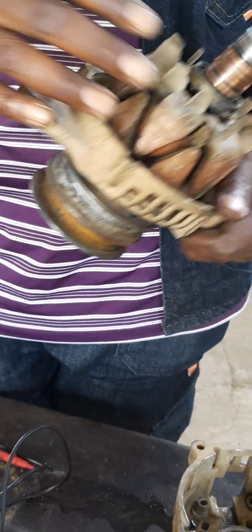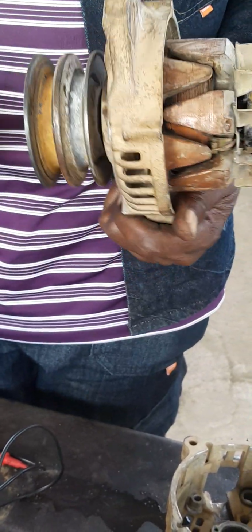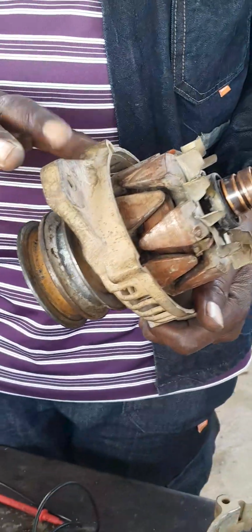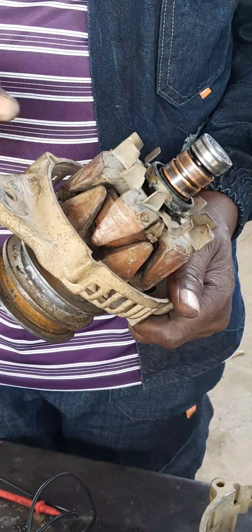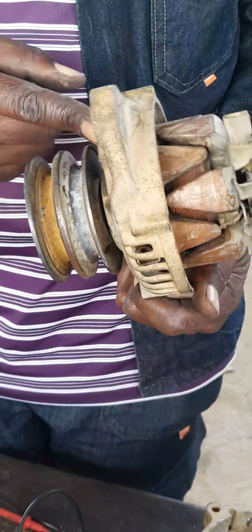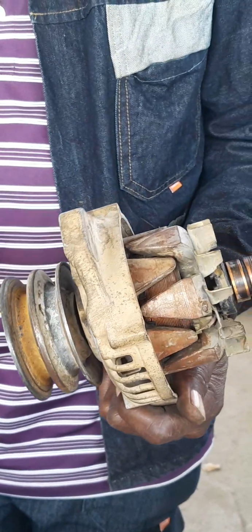It's a case of removing this very big bolt, removing the pulley, and pulling out the rotor. Then there are 3 screws where there is a bracket which retains the bearing inside the drive end bracket. Unscrew that, then punch from this side, and it will just go through the other end.